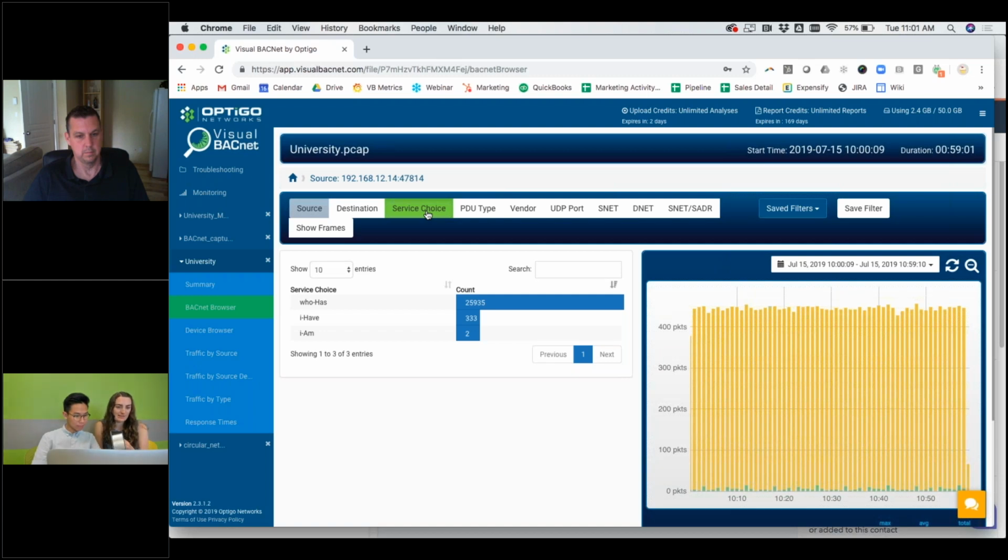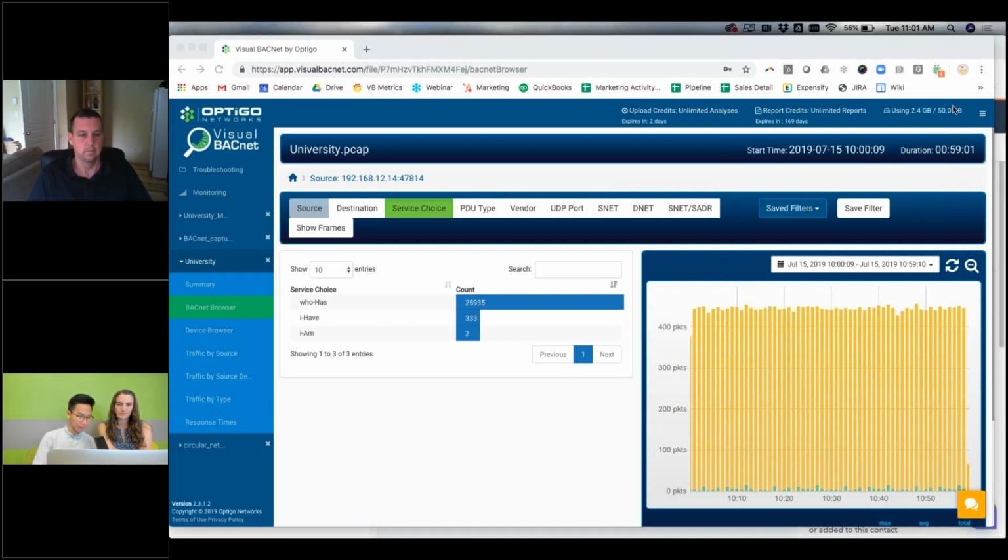Who has? Daniel, what's the who has packet? Who has is usually finding the device that has an object. So in this case, it might want to find who has a certain object name, and then it will be broadcast, and whichever device has that object name would respond with an I have.